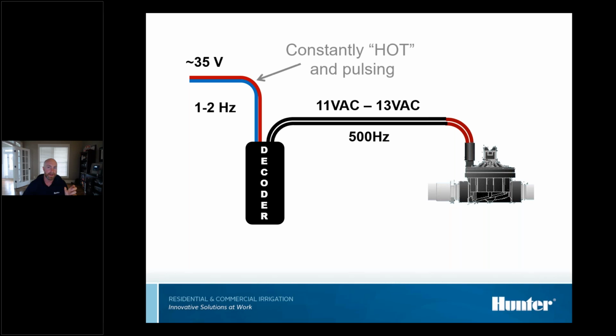One thing to keep in mind is that with a 2-wire controller, the 2-wire path is constantly hot and pulsing. It's not like a conventional system that only turns on when the system is running. With a 2-wire system, even when nothing's running, it's constantly pulsing and constantly sending data back and forth.